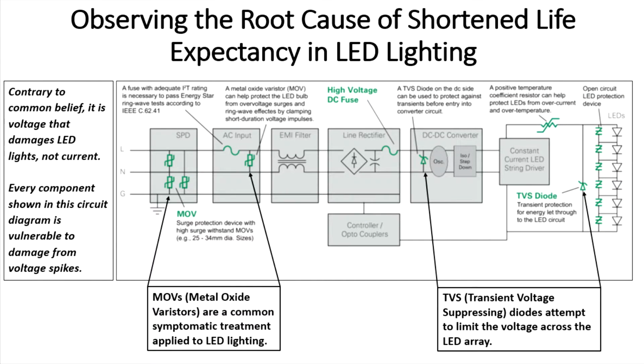LED lighting systems, even the lamps themselves, the light bulbs themselves, have a power supply or driver board installed in them, and they have a lot of different components. Most of them are for keeping the voltage equal and constant all of the time. They operate on direct current, so there are rectifiers to convert the AC to DC, and there are many different filters inside, as I've shown on this slide. The thing that affects these the most is voltage. Voltage affects virtually every aspect of them.